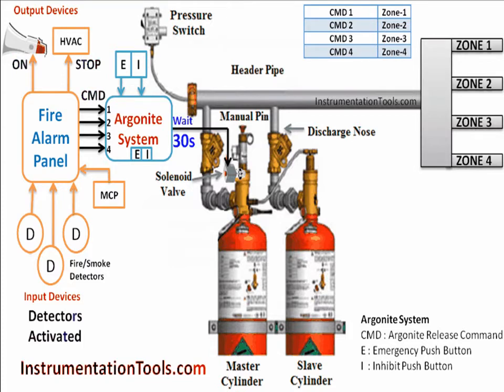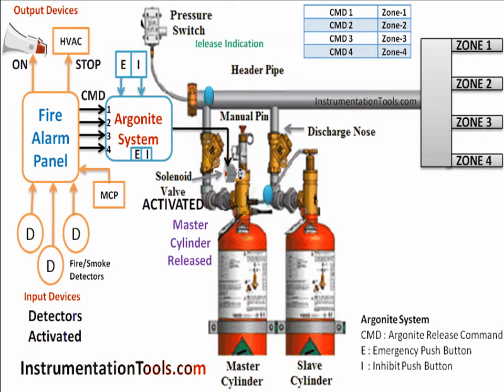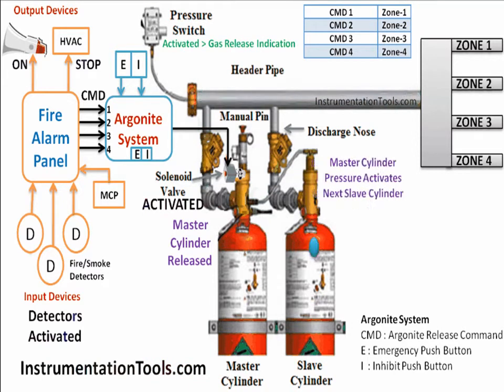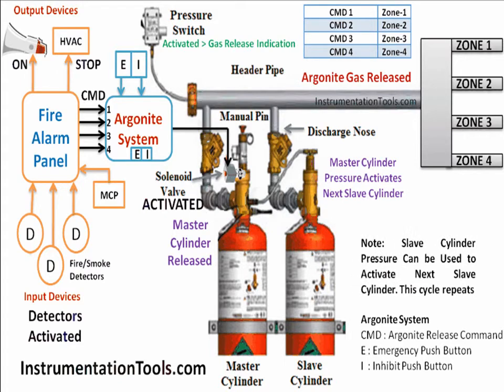The Argonite System waits for some time before releasing the Argonite cylinders — typically 30 to 60 seconds. Sometimes we receive false fire and smoke detector alarms. In that case, we need to inhibit the Argonite Release Command. Inhibit means stop the action. Inhibit push buttons are generally installed near the Argonite System or in respective zones, and are also provided on the Argonite panel as shown in the animation.